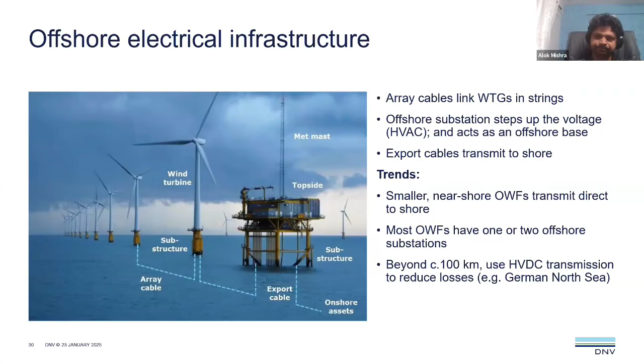When we talk about voltage level, the array cable was generally 32 or 33 kV in the early days. Now it's moving to 66, and the technology is also moving toward 132 kV, but at present the array cable is generally 66 kV. When we talk about export cable, it is generally 220 kV and beyond.